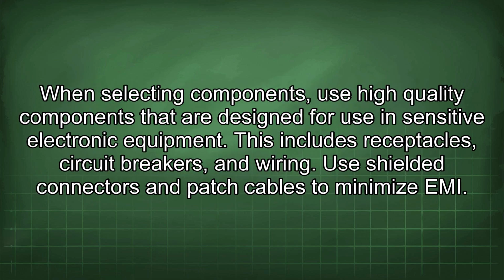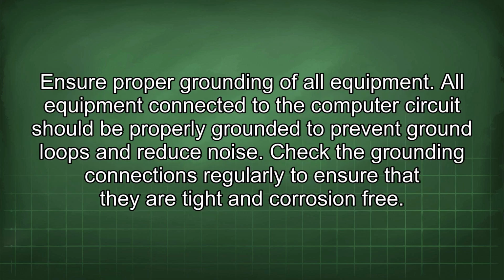When selecting components, use high-quality components that are designed for use in sensitive electronic equipment. This includes receptacles, circuit breakers, and wiring. Use shielded connectors and patch cables to minimize EMI. Ensure proper grounding of all equipment. All equipment connected to the computer circuit should be properly grounded to prevent ground loops and reduce noise. Check the grounding connections regularly to ensure that they are tight and corrosion-free.